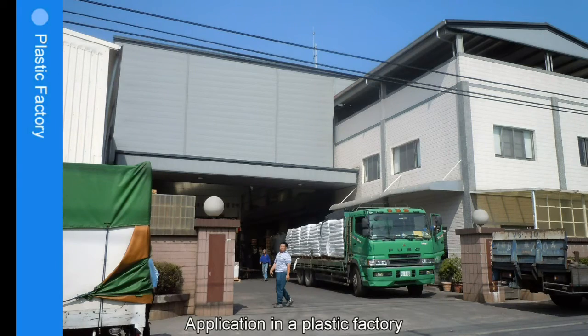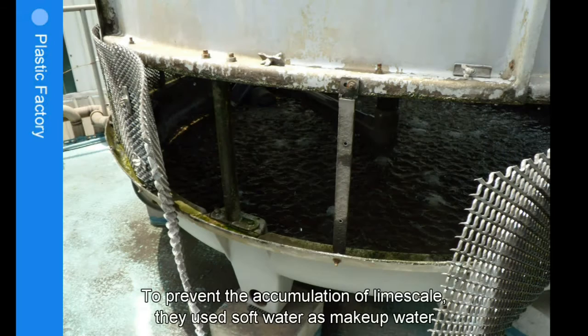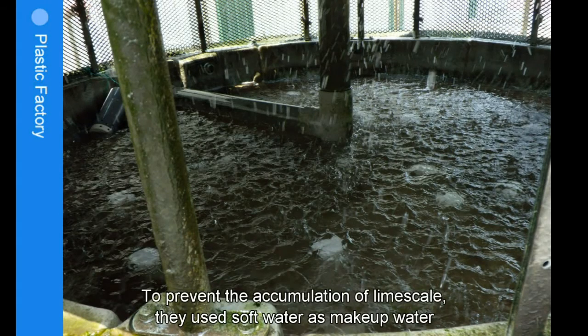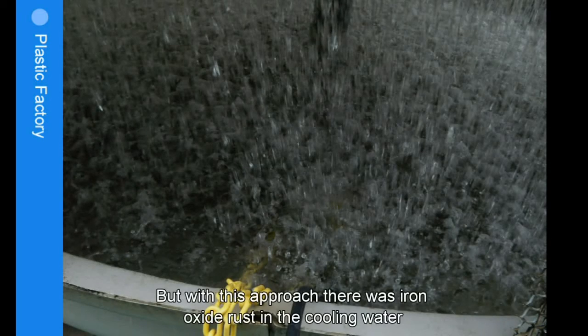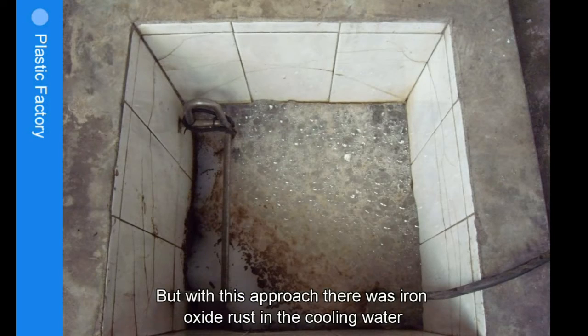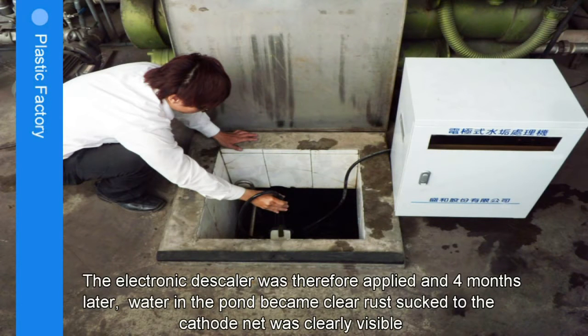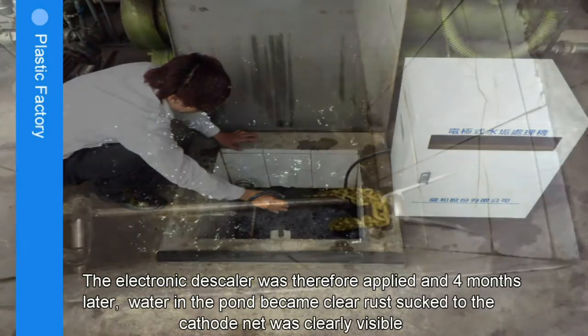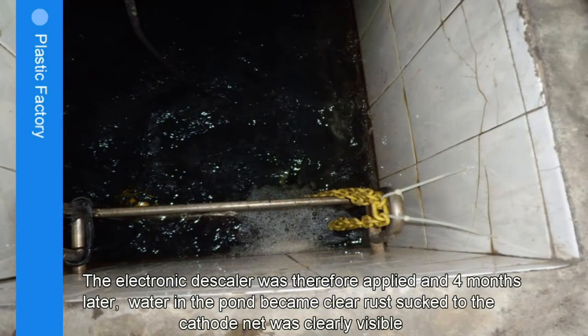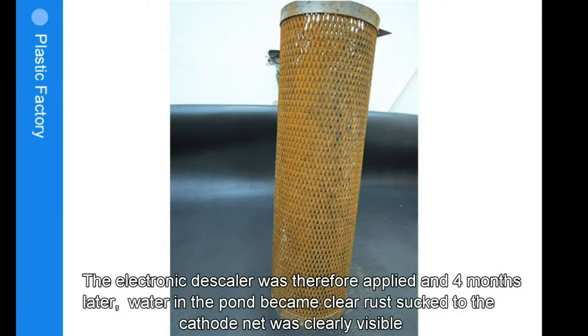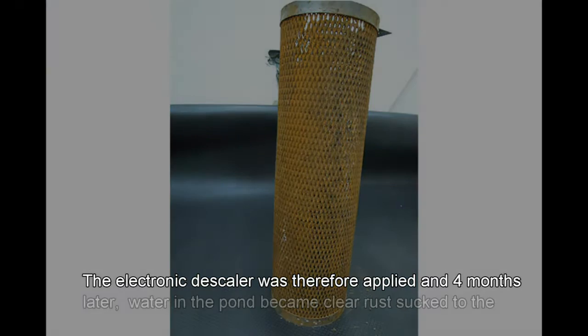Application in a plastic factory. To prevent the accumulation of limescale, they used soft water as makeup water. But with this approach, there was iron oxide rust in the cooling water. The electronic descaler was therefore applied, and 4 months later, water in the pond became clear. Rust sucked to the cathode net was clearly visible.